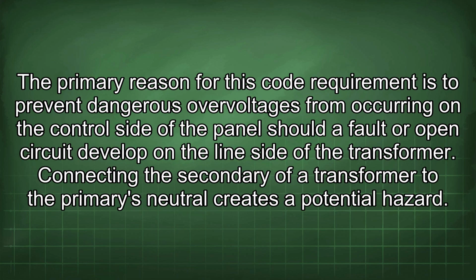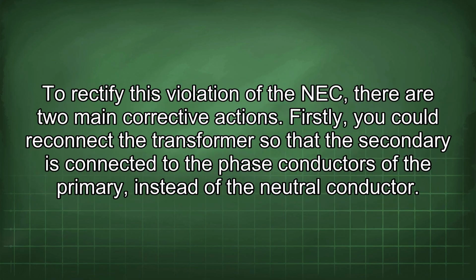The primary reason for this code requirement is to prevent dangerous overvoltages from occurring on the control side of the panel should a fault or open circuit develop on the line side of the transformer. Connecting the secondary of a transformer to the primary's neutral creates a potential hazard. To rectify this violation of the NEC, there are two main corrective actions.